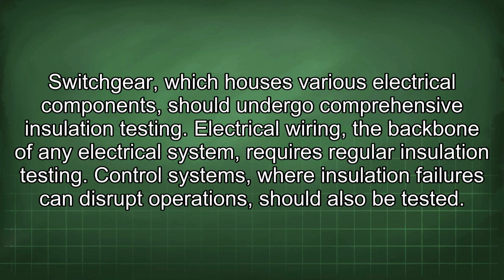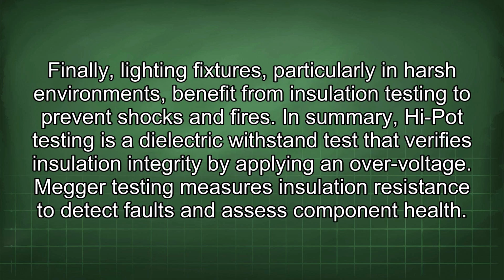Switchgear, which houses various electrical components, should undergo comprehensive insulation testing. Electrical wiring, the backbone of any electrical system, requires regular insulation testing. Control systems, where insulation failures can disrupt operations, should also be tested. Finally, lighting fixtures, particularly in harsh environments, benefit from insulation testing to prevent shocks and fires.